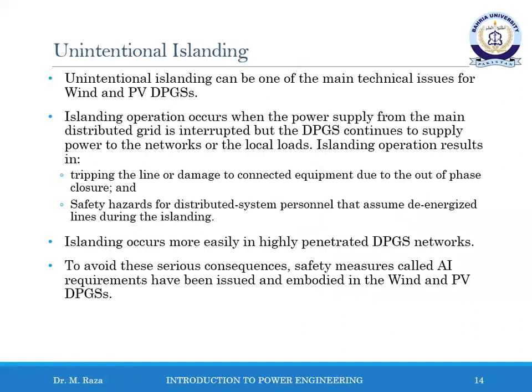Unintentional islanding can be one of the main technical issues for wind and PV distributed power generation systems. Islanding operation occurs when the power supply from the main distribution grid is interrupted, but the distributed power generation system continues to supply power to the network or the local load. Islanding operation results in tripping of the line or damage to connected equipment due to out-of-phase closure, and a safety hazard for distribution system personnel who assume the line is de-energized during the island.